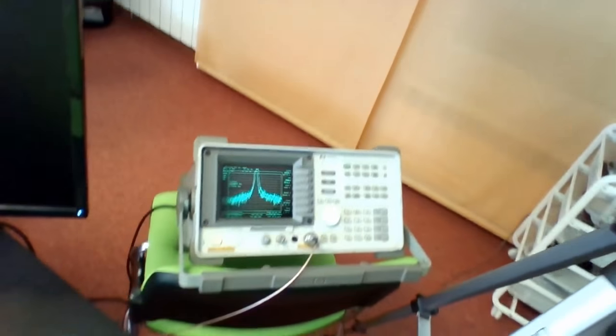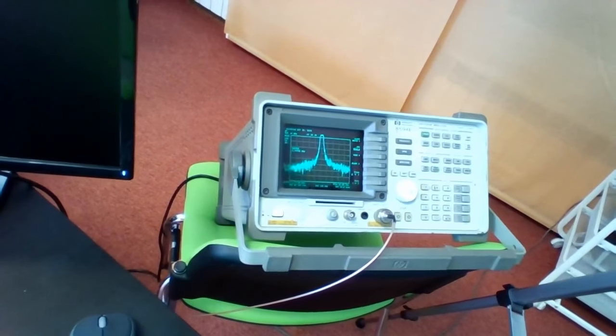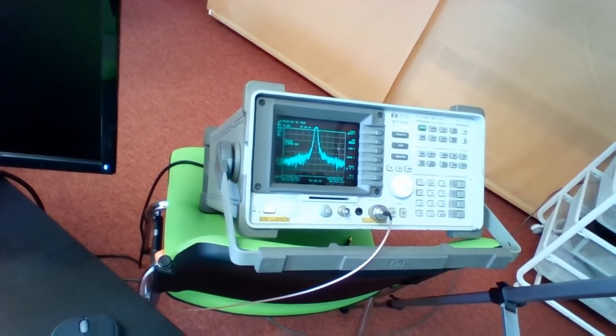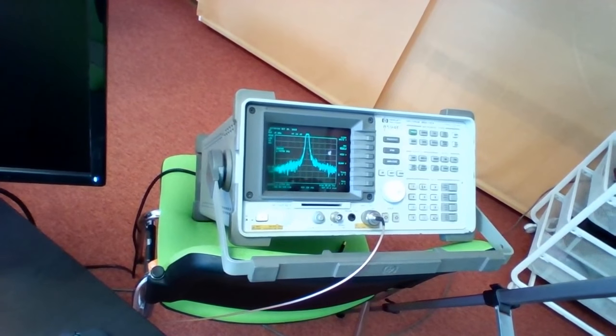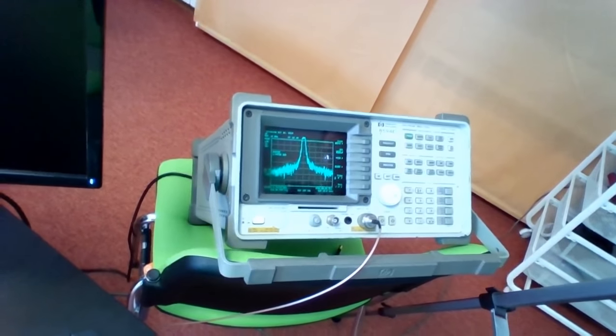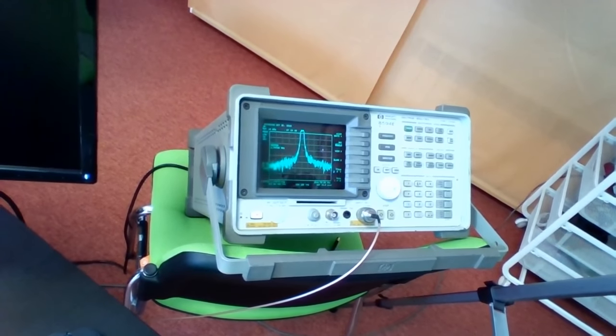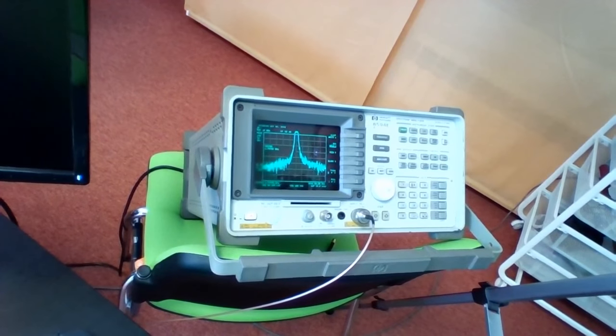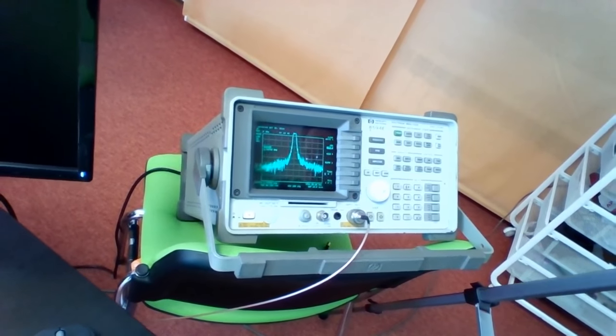So here's our system. Here we have the spectrum analyzer showing the emissions from the device under test during the time that we've been, since the webinar started about 20 minutes ago. This is a band 3 device. You can see center operating at 1.74 gigahertz.